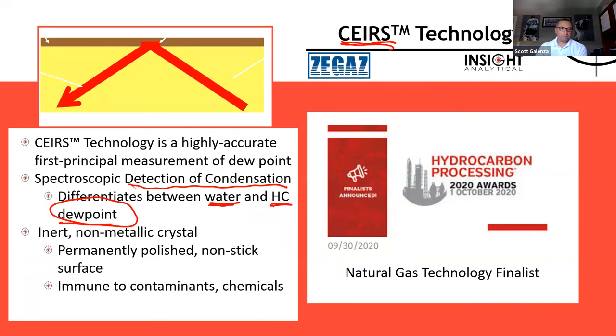Perfect. And then Phil, there's another one in the chat from Naya. How about sample lag time, since molecules will move slowly at higher pressures? Yeah, that's a good question. Nayef is asking about the lag time for moving the sample over to the analyzer. When we keep gas at high pressures, it's compressed when it's in the tubing, but we measure the flow at low pressures at the flow meter. So we go, well, I've got a liter a minute of flow, that's lots. Well, when it was at 60 bar, it was compressed by a factor of 60. So it can move quite slowly.